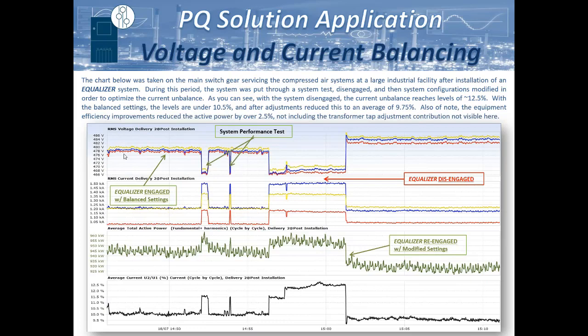And when we first did the baseline measurements, they were actually running during nominal load at about 495, because whenever one of those air compressors came online, it would drop that voltage to about 465, 470. So they wanted to make sure that it didn't trip anything out on the network.